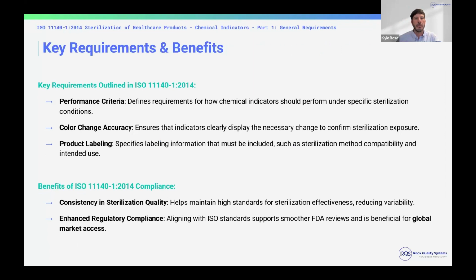Some of the key requirements and benefits that are outlined in the standard. So defining the performance criteria: requirements for how these chemical indicators should perform under specific sterilization conditions, ensuring there's color change accuracy. So making sure there's a clear display with the chemical indicator, both before it's been sterilized and after sterilization, or ensuring that you met your sterilization assurance level. Making sure you have product labeling on these chemical indicators that shows what information must be included, such as the sterilization method compatibility, intended use, things like that. So making sure that the chemical indicators themselves meet the labeling requirements of 11140.